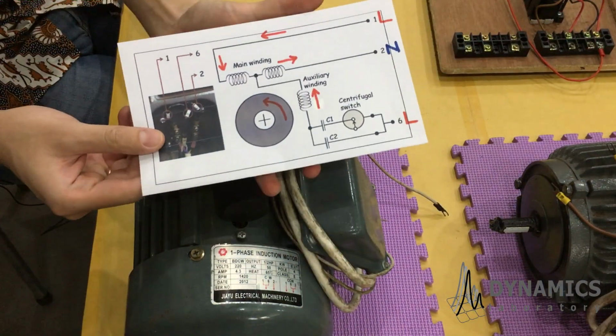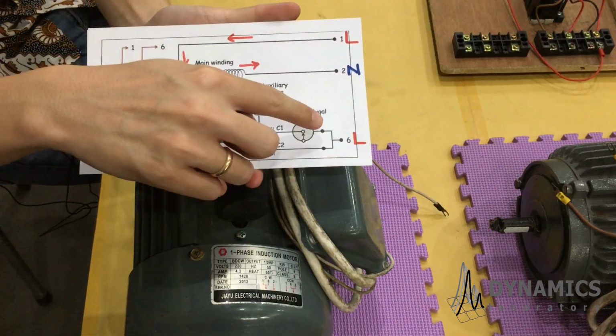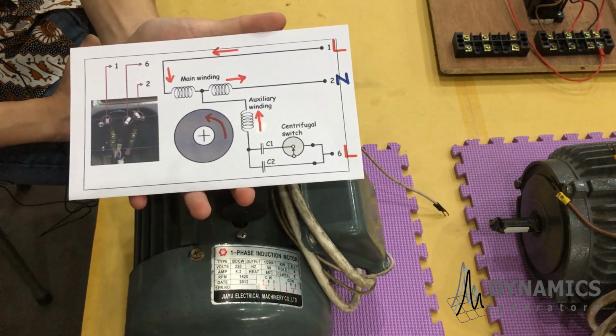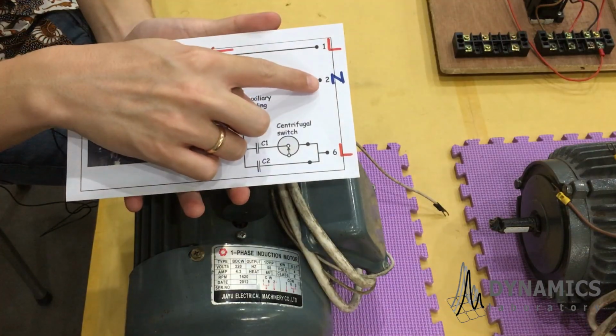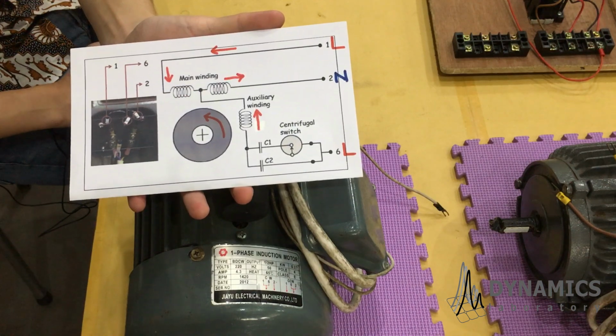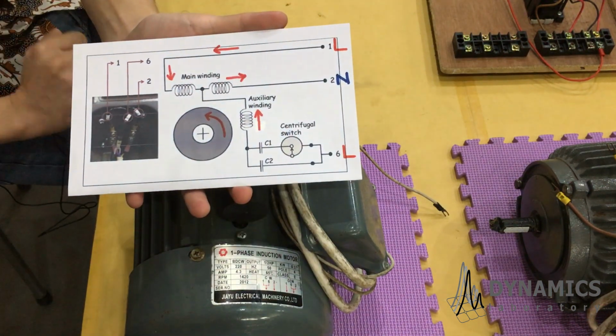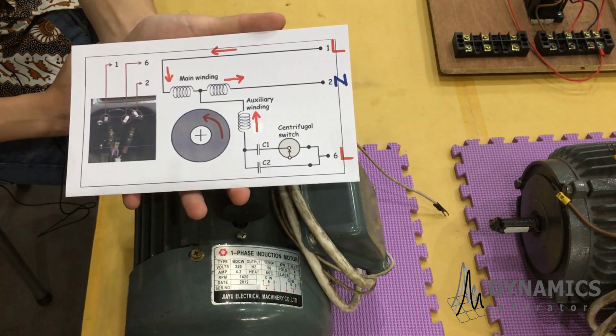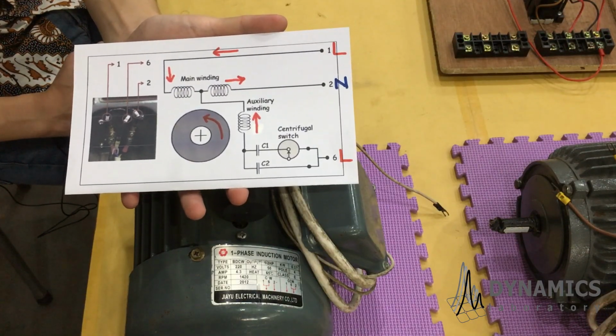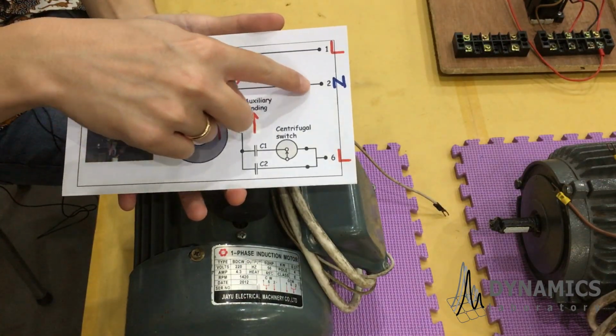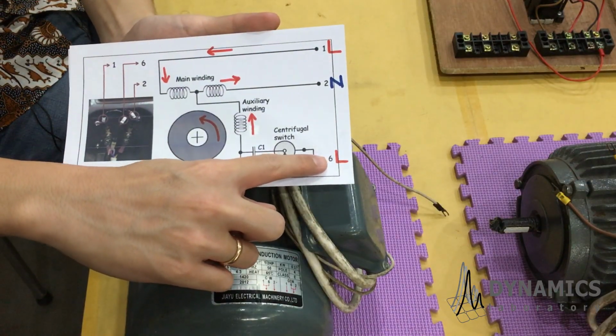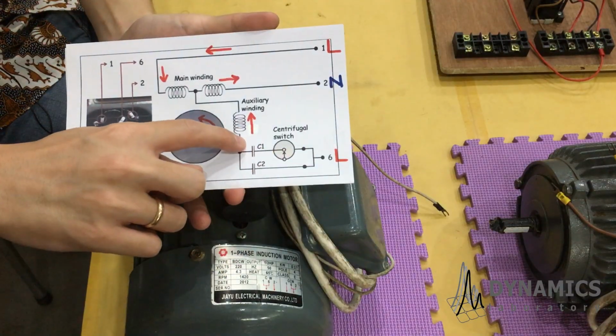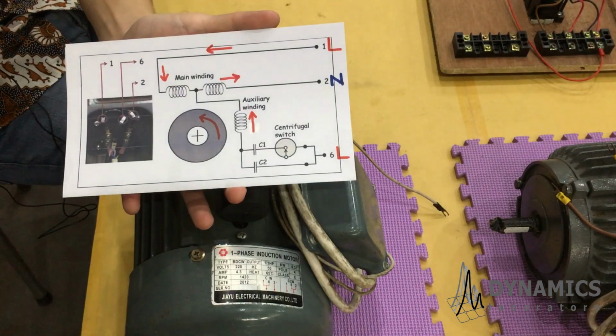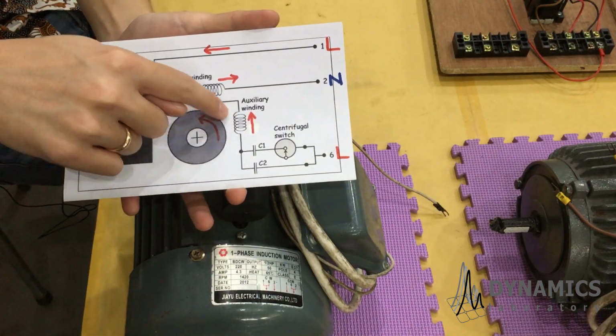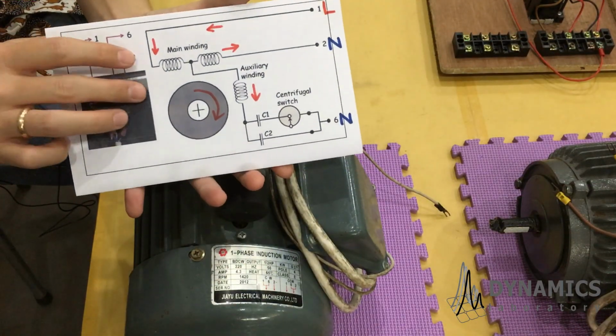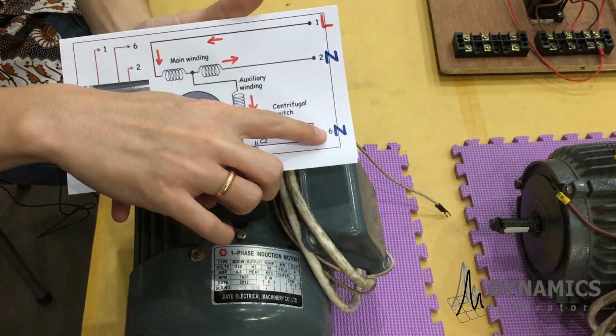Let's look at the diagram. Cable 1 and cable 2 are the main winding. Meanwhile, cable 6 is the auxiliary winding. We connect cable 1 with the live terminal and cable 2 with the neutral terminal. And for example, I connect the auxiliary winding with the live terminal. Thus, the current will flow from live to neutral terminal and the motor will rotate counterclockwise. You see, from the live terminal to the neutral terminal, and also the auxiliary winding is connected to the live terminal. That's why current will also flow from here to the neutral terminal. That's why the motor will rotate counterclockwise. After that, what if we connect the auxiliary winding with the neutral terminal?